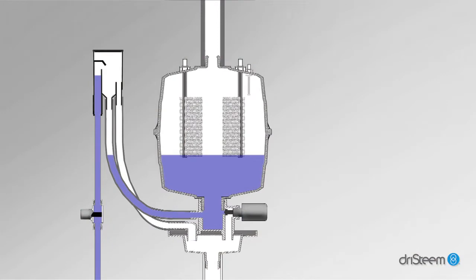When the relative humidity level in the humidified space drops below the set point, the humidifier's onboard vapor logic controller receives a call for humidity and energizes the electrodes.